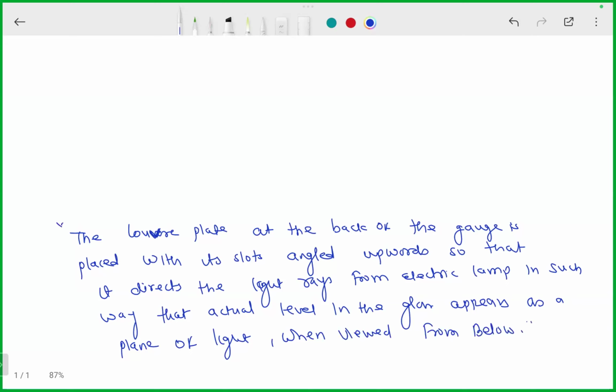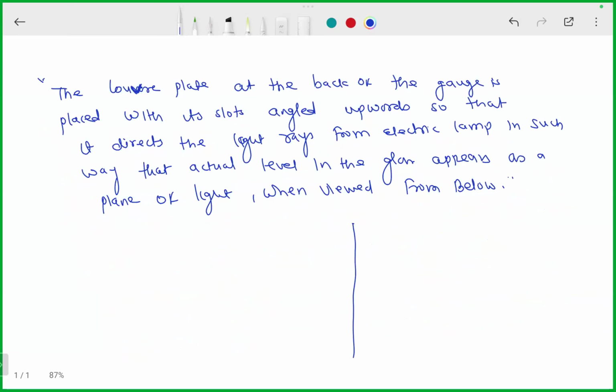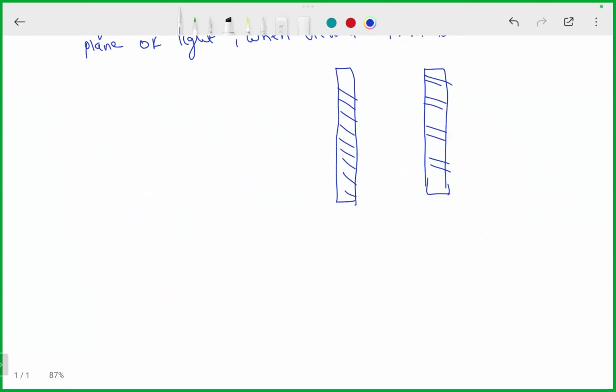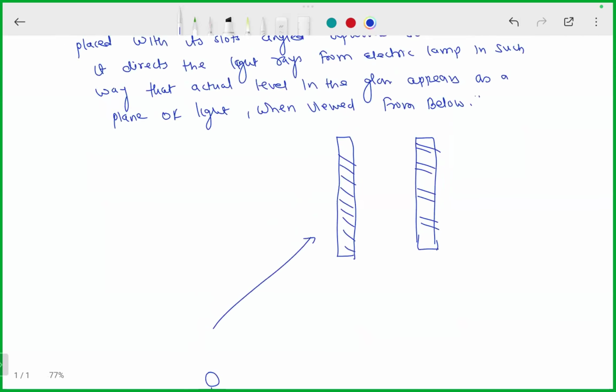So there are two arrangements. This plate, positioned at the back of the gauge glass, is going to have slots like this, or it can be painted in black and white color. What's the advantage of this? If somebody is standing down and looking at the glass, because of this particular refractive pattern, when looking at the gauge glass from below, he will be able to see the level correctly. In a normal gauge glass, if you look at the level from below, it will not be possible to see it. But in this double plate type of water level gauge, you will be able to see it - that is the advantage here.